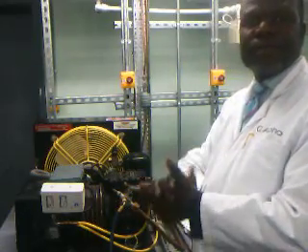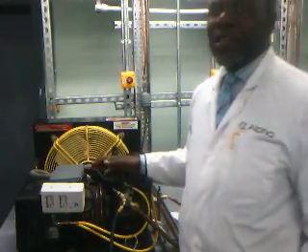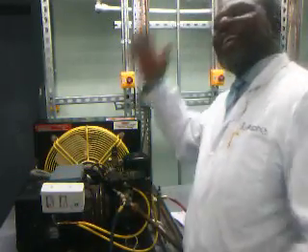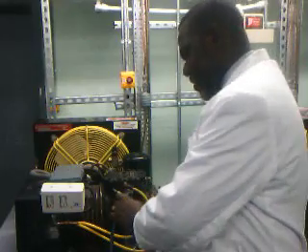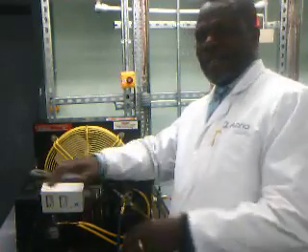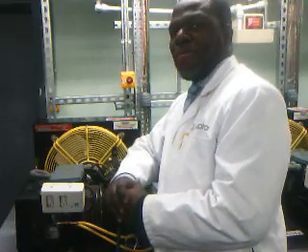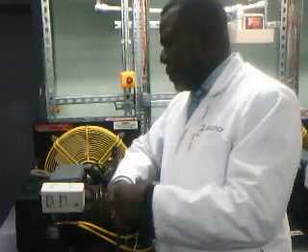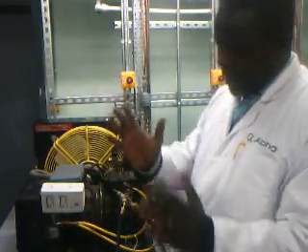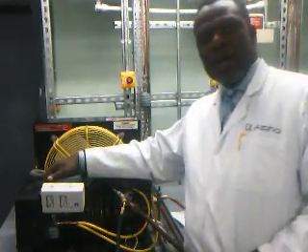Okay, any more? So overcharge, what do you want to do if you do? If you overcharge the system, you have to recover part of the refrigerant. People used to let the gas out, slacken the valve a bit, open it, and the gas goes out. But that has to stop because of climate change and all that. So now the laws are being enforced, and we have to follow the law. So you need to recover. Get your cylinder, get your scale, and then recover the amount that you need based on what you've detected, and then you carry on. Any more questions?